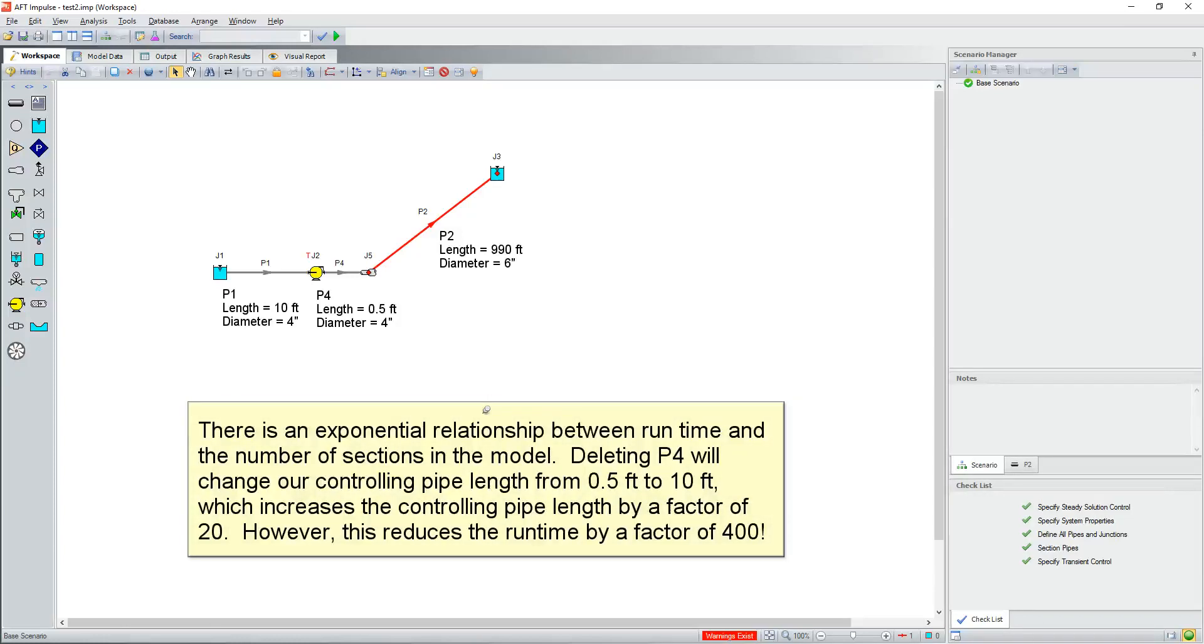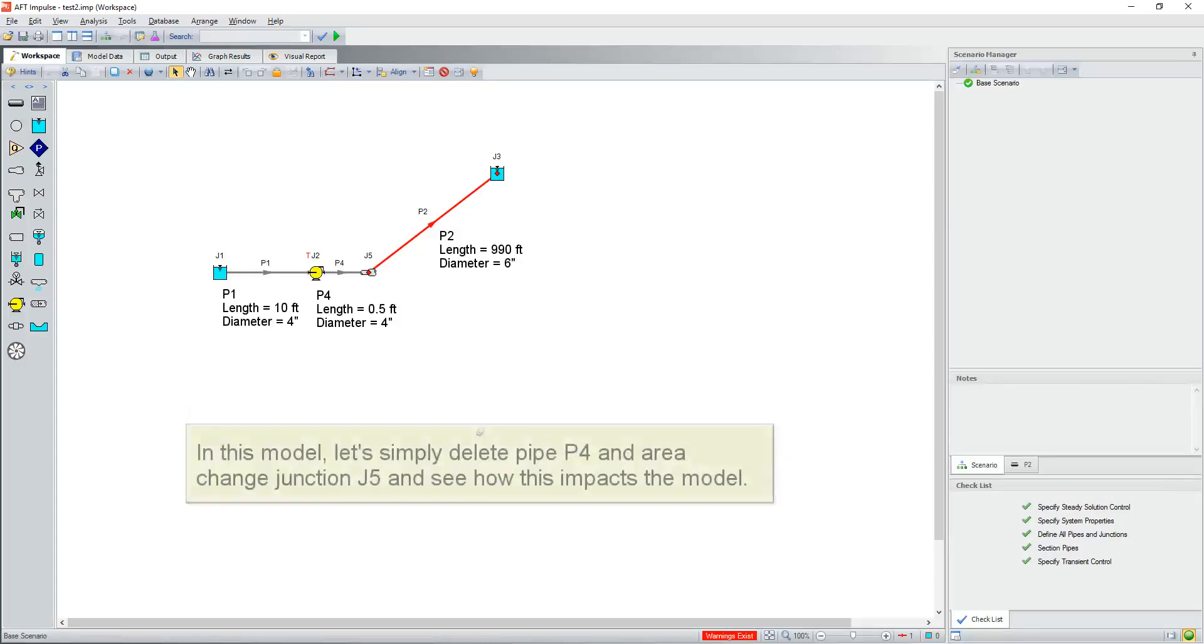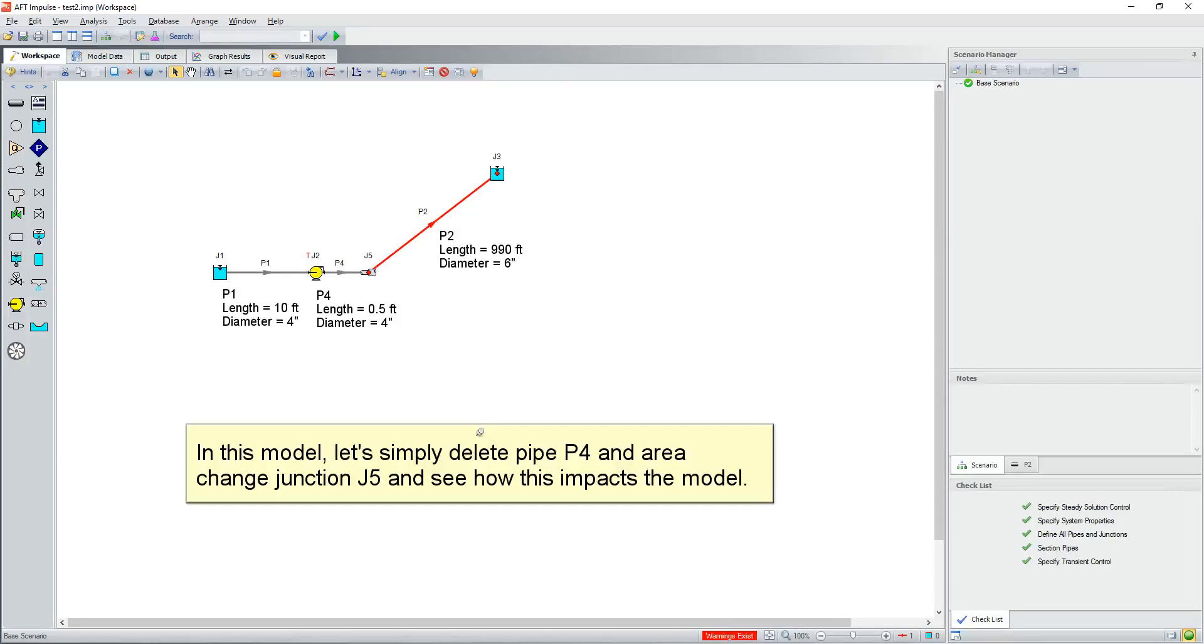Deleting P4 will change your controlling pipe length from half a foot to 10 foot, which increases the controlling pipe length by a factor of 20. However, this reduces the runtime by a factor of 400. In this model, let's simply delete pipe P4 and the area change junction J5 and see how this impacts the model.